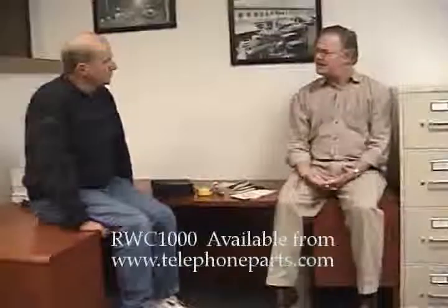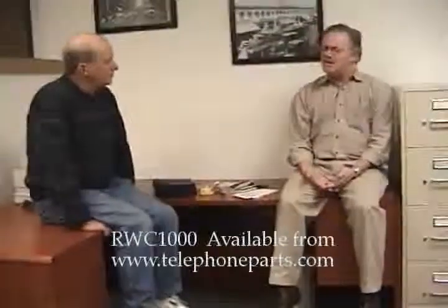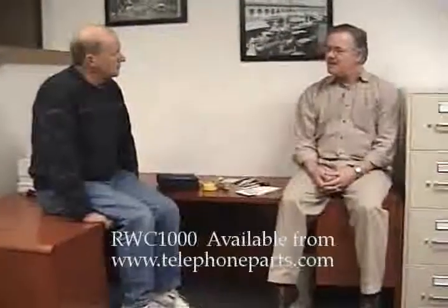And these people ask the question, what is the difference between a Real World Certifier and a standards-based certifier? Well, a standards-based certifier uses high-speed analog signals to test cables. The Real World Certifier does it with digital signals. We look at particular cable parameters and we compare those to a database that we have stored on the tester. The results are displayed as cable category and predicted cable speed.